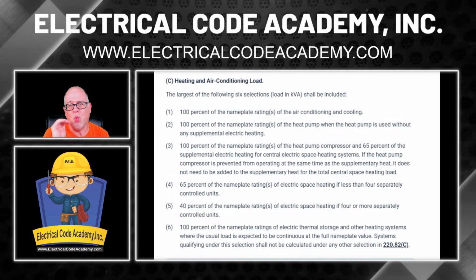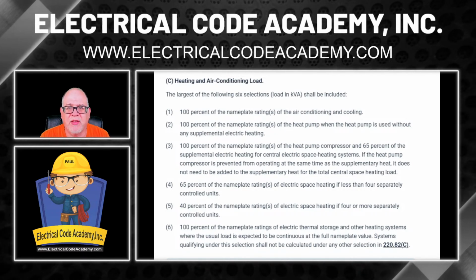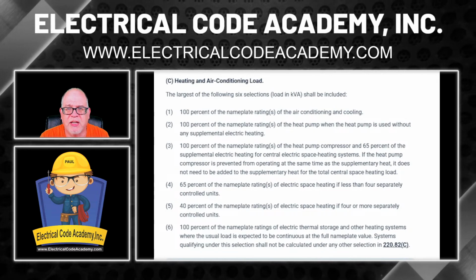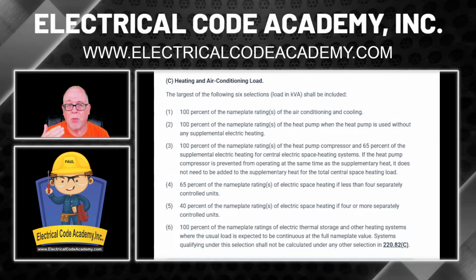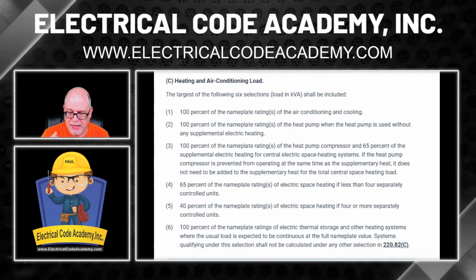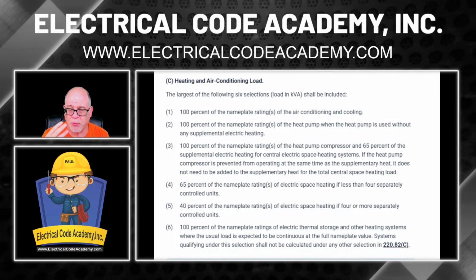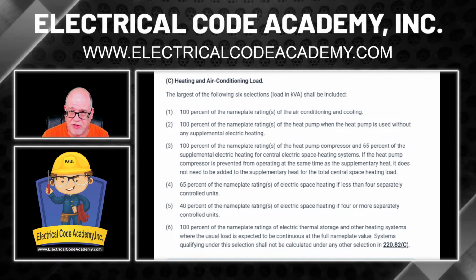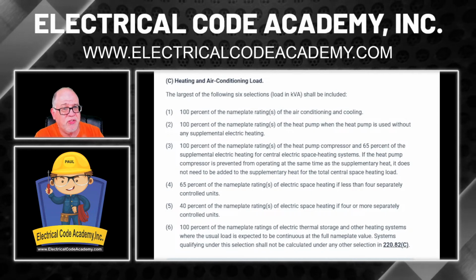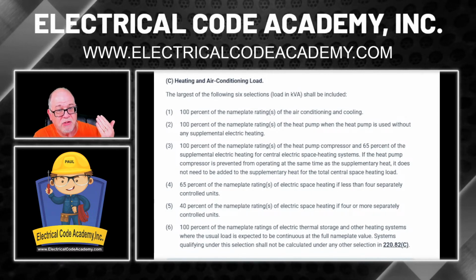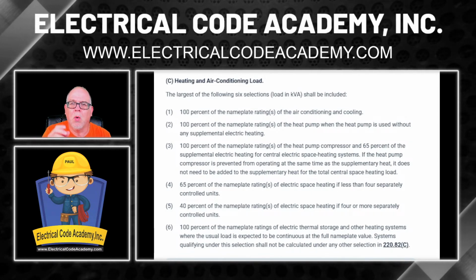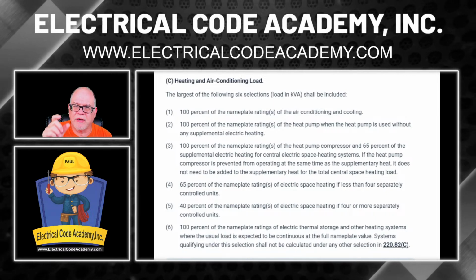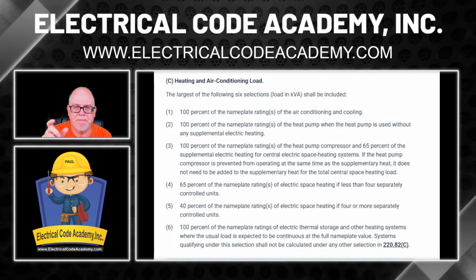Number 1 on this list says 100% of the nameplate ratings of air conditioning and cooling. We already know what our air conditioning is. We had 2 of them at 10.5 amps and 3 of them at 7.2 amps. And we know our heat: there were 6 of them at 3 kW each. So when it comes to the AC, we're going to take its full value at 100%.